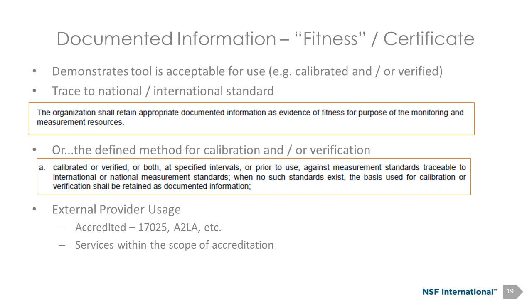One of the things we wanted to talk about here is if we're outsourcing, within that certificate or on that certificate, we probably want to ensure that the certificate has some evidence to show that the provider is A2LA or accredited to perform the function. It may link to their company name, and then we go look at their accreditation profile and see that they're capable of doing that particular style of device or that particular instrument. I can tell you that I've been on audits where we pulled tools and pulled the certificates for those tools, and then we looked up the third-party provider for the calibration effort and found that they weren't accredited to perform the calibration of those particular devices.